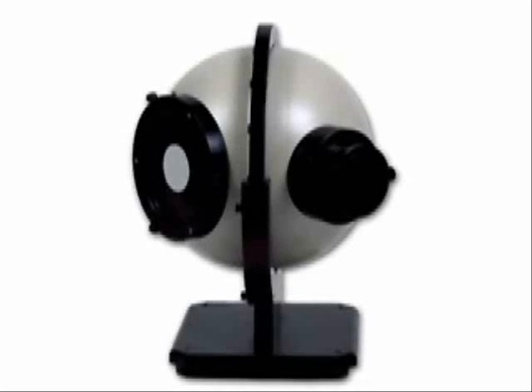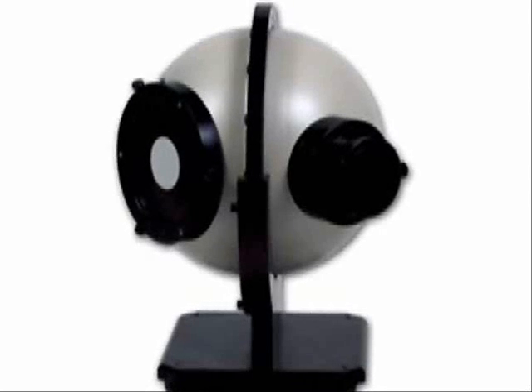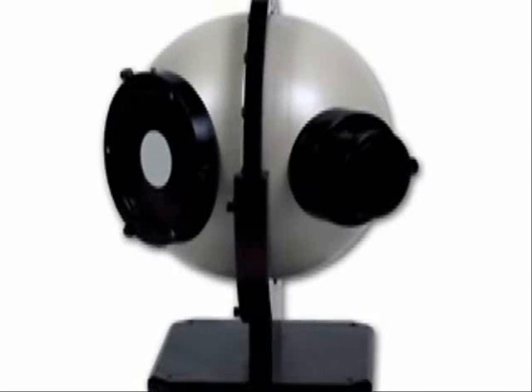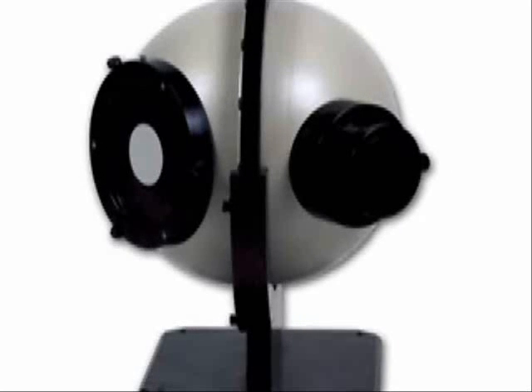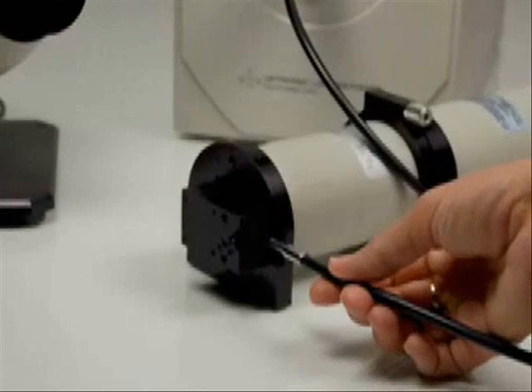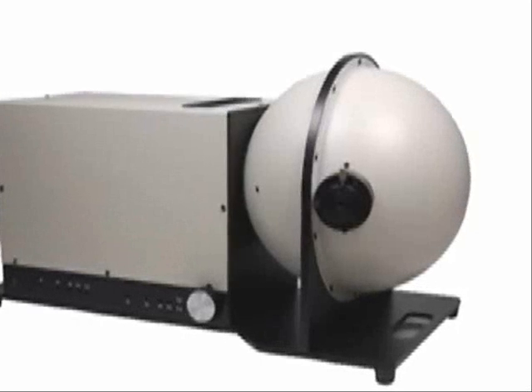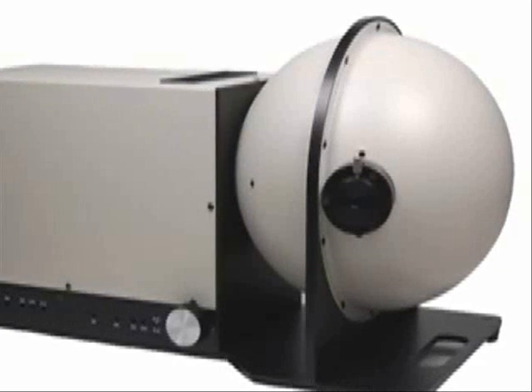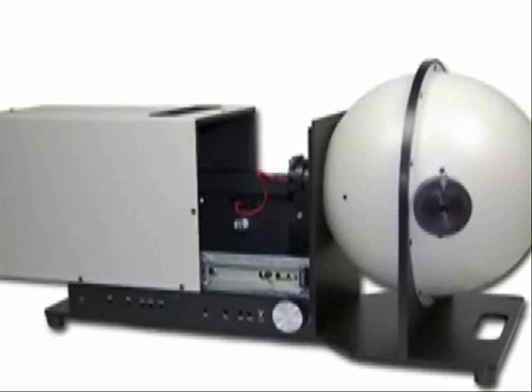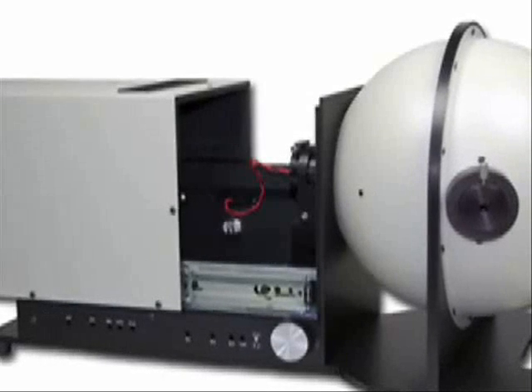A host of accessories are available for the OL-770, many which meet CIE standards, such as the OL-IS-670 Integrating Sphere used for making total spectral flux measurements, the OL-15AB LED Receptor for measuring intensity of LEDs, and the OL-1272 LED Partial and Total Flux Integrating Sphere, designed specifically to meet CIE 127.2 measurement recommendations for total luminous flux and partial LED flux measurements.